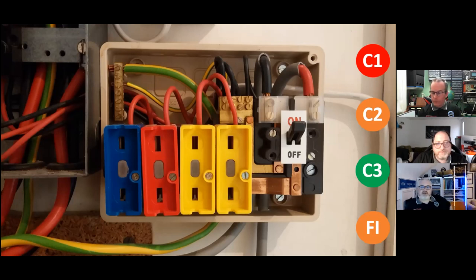Can we also chuck into the debate the guidance on identification of conductors within boards and the now requirement to have both sheaths all the way up to the terminal themselves? Years ago, was that in the regs or the guidance notes? Remember, where these were selected and erected on previous editions, it may have been compliant. But we are inspecting to current regs. But it's all good debates to have within the brain.